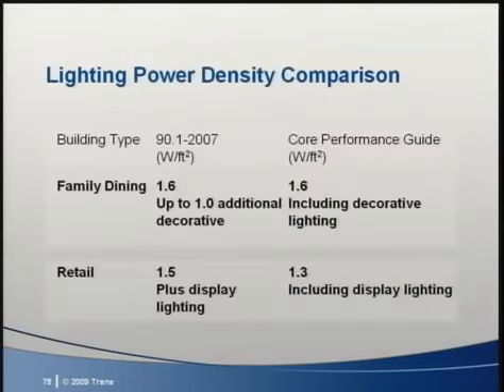Here are two examples. Family dining is allowed 1.6 watts per square foot in both 90.1 2007 and the Core Performance Guide. But in the CPG, any decorative lighting, such as sconces, are included in the lighting power allowance. For retail, 90.1 allows 1.5 watts per square foot plus lighting to highlight merchandise. The CPG only allows 1.3, and that includes display lighting. Therefore, in many cases, the lighting power for general lighting of the space must be lower in the Core Performance Guide than 90.1 2007.